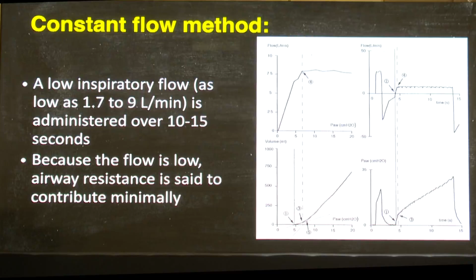There is another technique called the low flow technique, where you are basically providing a very low flow of 1.7 to, like, 8 liters. 8 liters is a little on the higher side. It is like 1.7 to 3 liters per minute at a very slow rate, and then you generate a PV loop.